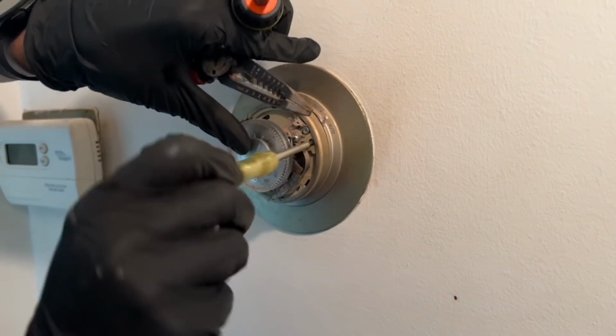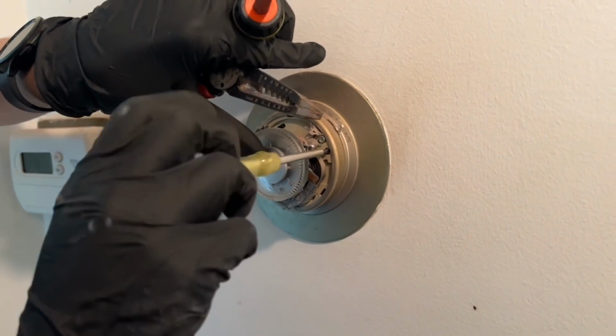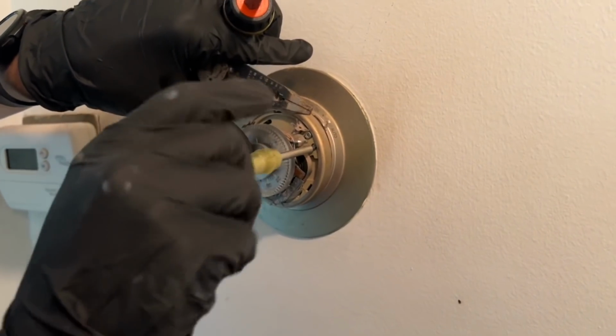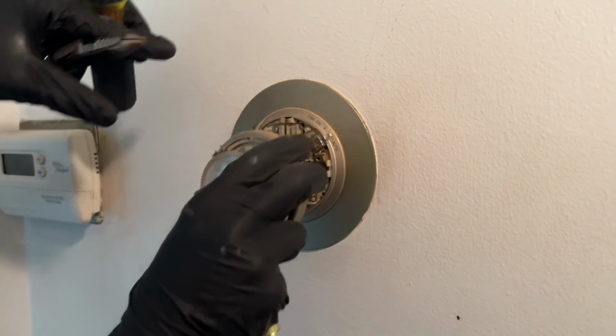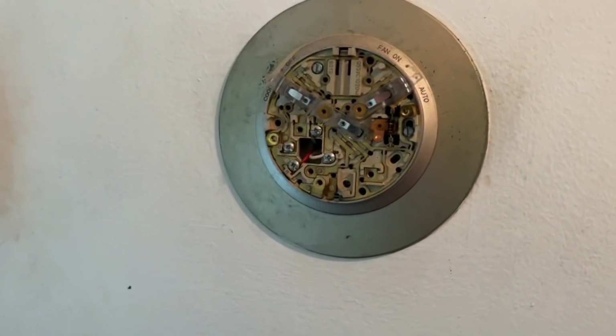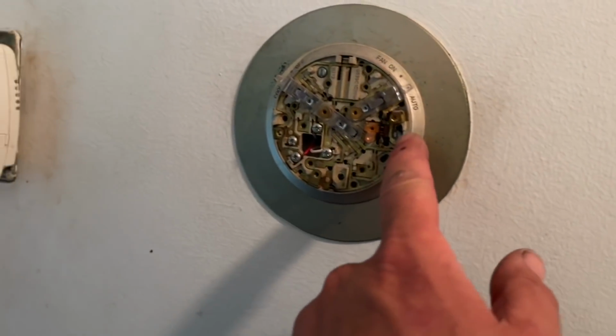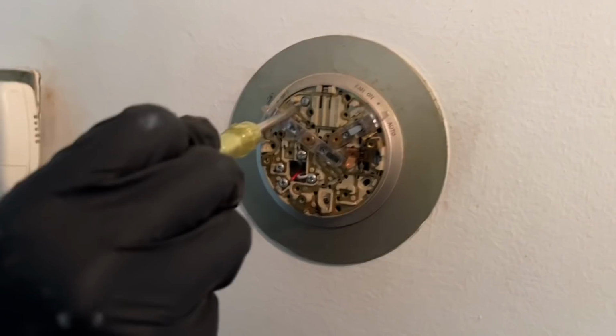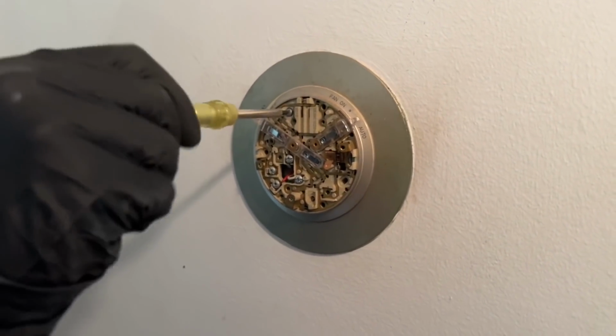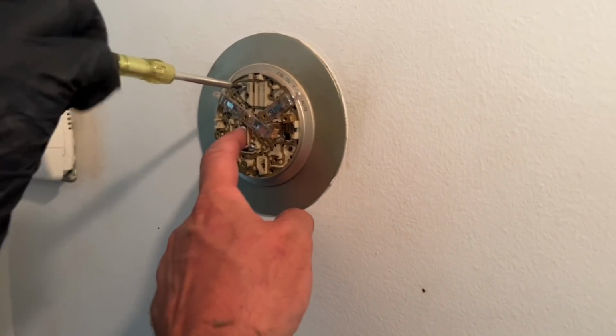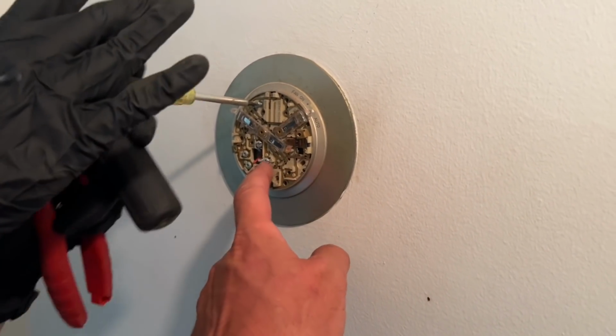Touching these scares me on a service call. Why, because it'll break? Feels like it'll break and that's it. Just don't drop it on the floor and break the mercury all over the guy's floor. Now there's a screw there and a screw there, we'll take the base plate off, then take out the 2 Phillips screws—3, because we have R, white, and green.